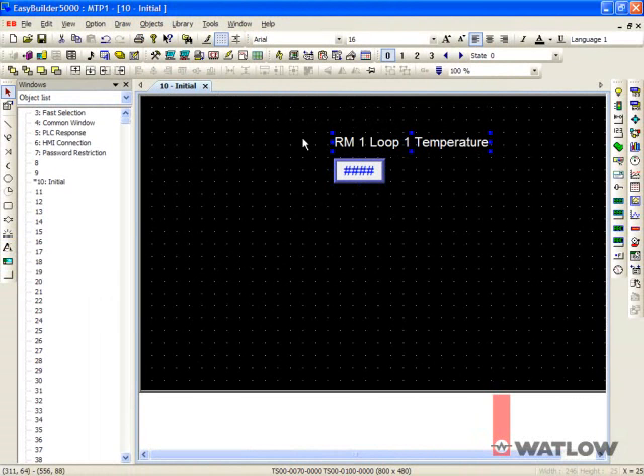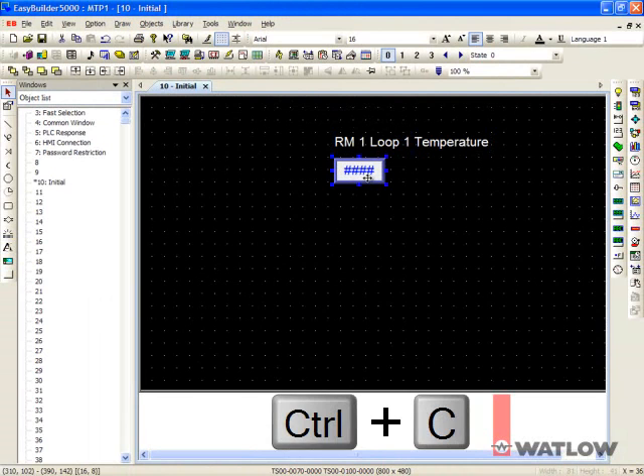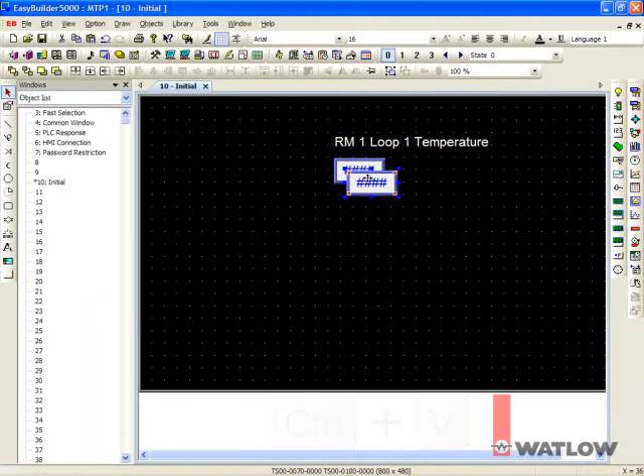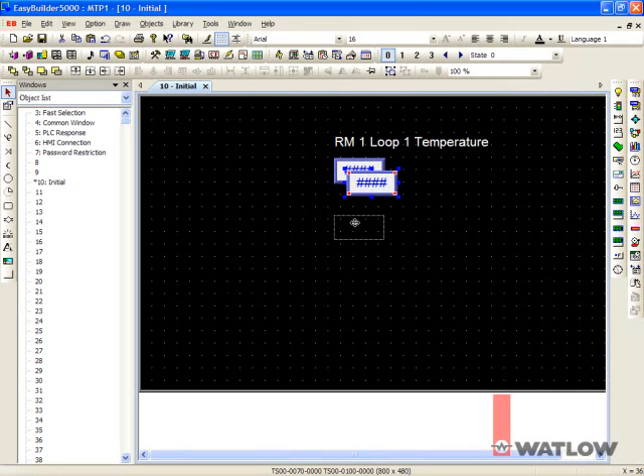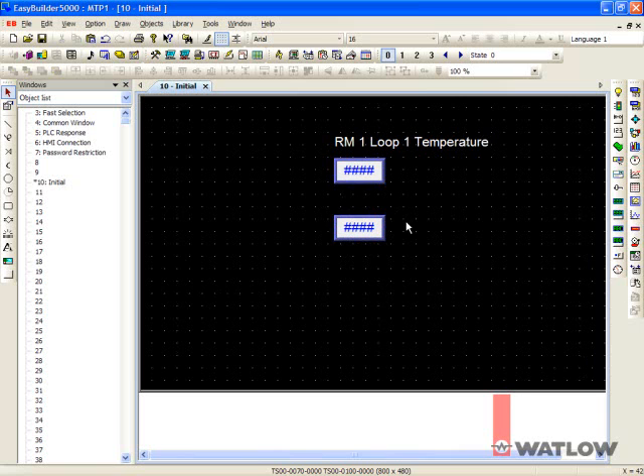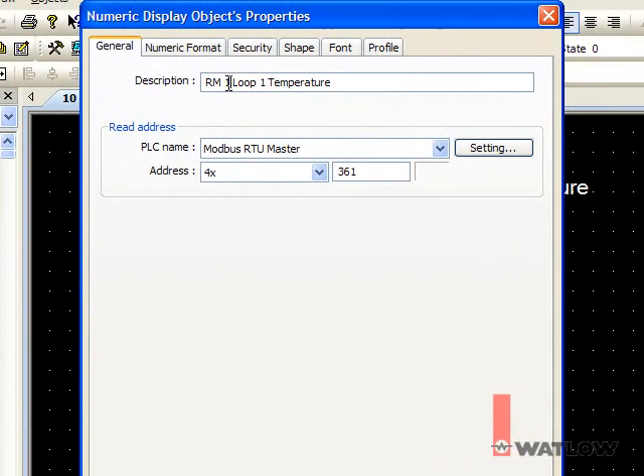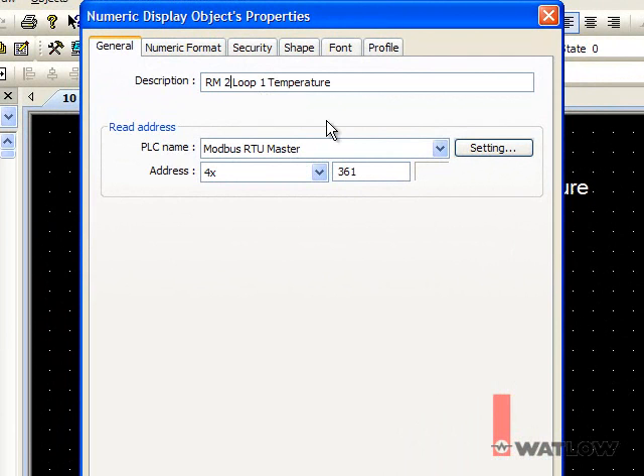You can go through the same steps to create another field for the second control module, but it's easier to copy and paste. Select the first field, press Ctrl-C to copy, and Ctrl-V to paste. Put the copy where you want it, then click the background to deselect it. Now double-click the copy to edit its settings. Change the description and the address. The address of the first loop's process value in the second control module is offset by 5000, since that's what we set the offset to in the gateway. So insert a 5 to make it 5361.